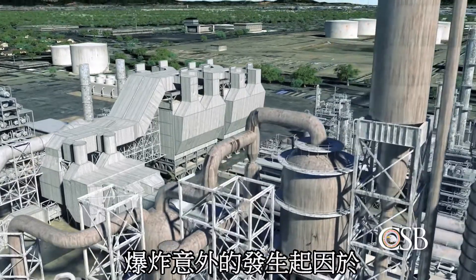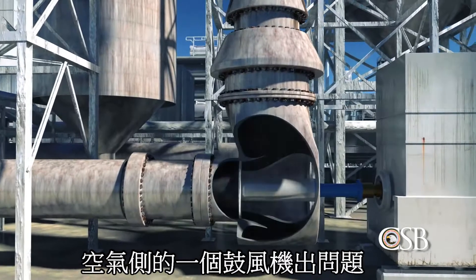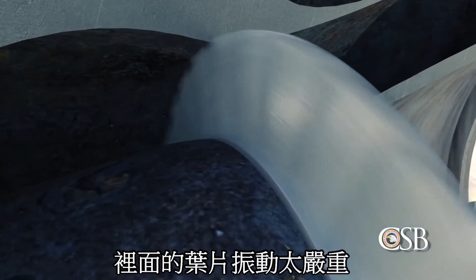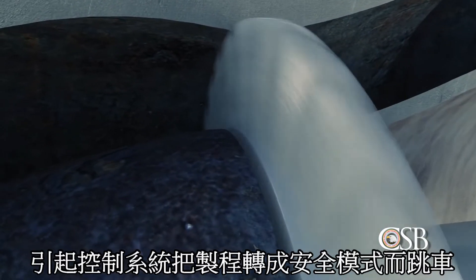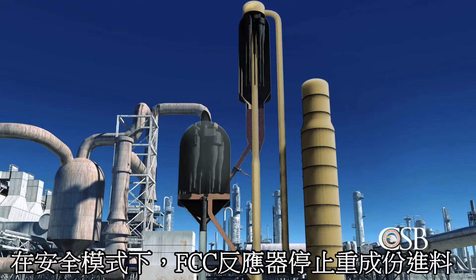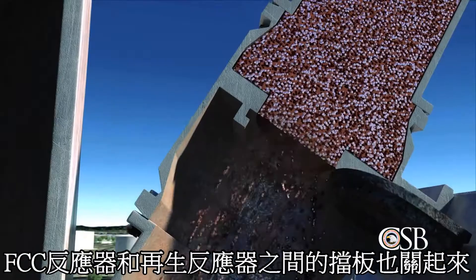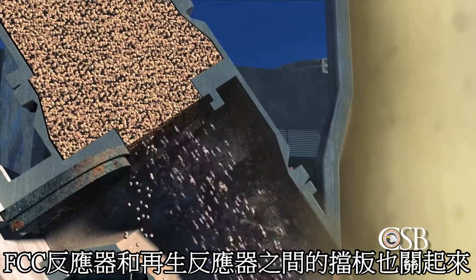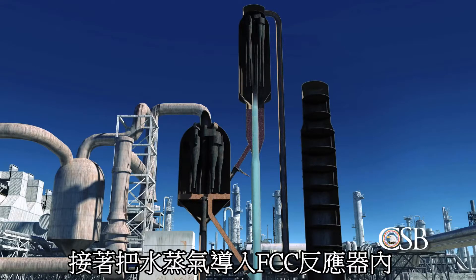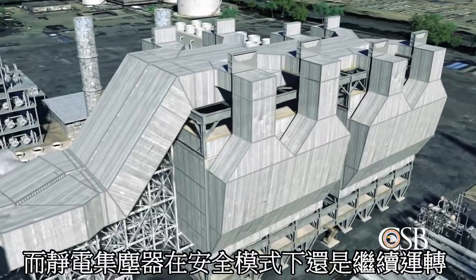The sequence of events that eventually led to the explosion began on Monday, February 16, 2015, when a piece of equipment in the air side of the FCC unit called the expander vibrated forcefully enough that the refinery's control system automatically transitioned the FCC unit to a standby mode known as safe park. During safe park mode, the flow of hydrocarbons into the reactor is turned off, the flow of air into the regenerator is also stopped, and the two slide valves connecting the reactor and regenerator are closed to ensure a catalyst barrier is maintained. Steam is then forced into the reactor to prevent hydrocarbons in the main distillation column from flowing back inside. The ESP remains energized during safe park.